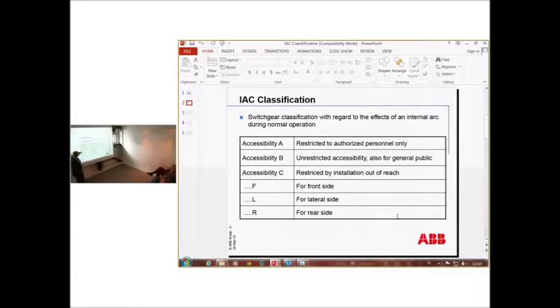And then there is accessibility A and B. A is the operator in front. So if I were the operator, I would be 20 centimeters from the switchgear and operate. B is unrestricted accessibility for the general public. This would be if this was in the middle of Reykjavik. Anyone can sit next to it and have a picnic or park their bike. So the switchgear is tested according to A, and the compact substations need to be tested according to B.